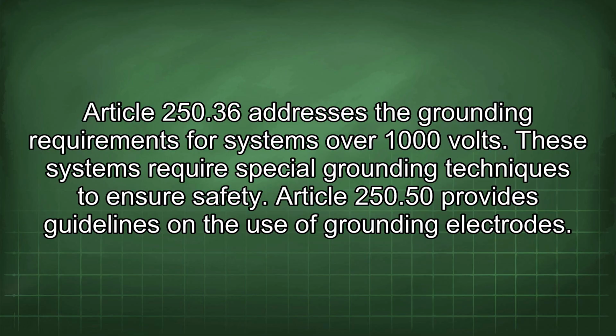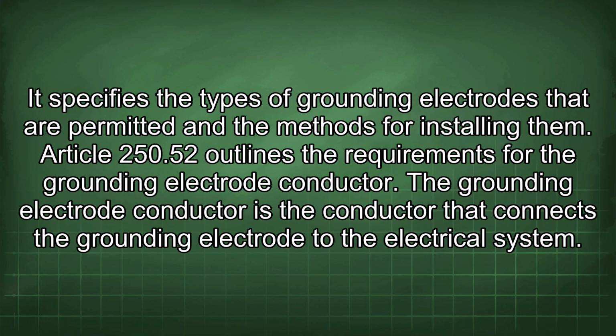Article 250.50 provides guidelines on the use of grounding electrodes. It specifies the types of grounding electrodes that are permitted and the methods for installing them. Article 250.52 outlines the requirements for the grounding electrode conductor. The grounding electrode conductor is the conductor that connects the grounding electrode to the electrical system.